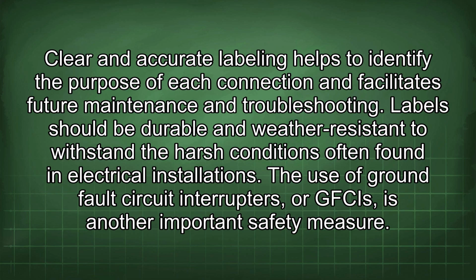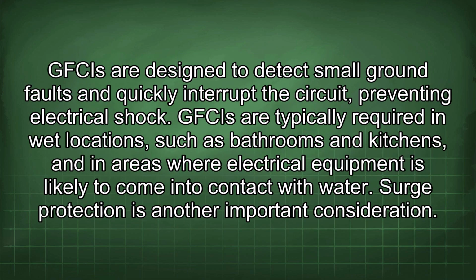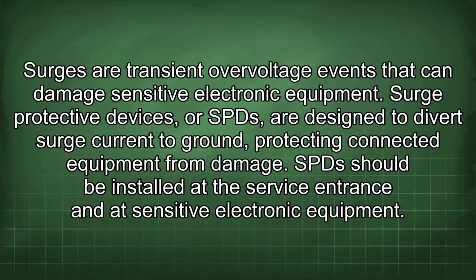The use of ground fault circuit interrupters, or GFCIs, is another important safety measure. GFCIs are designed to detect small ground faults and quickly interrupt the circuit, preventing electrical shock. GFCIs are typically required in wet locations, such as bathrooms and kitchens, and in areas where electrical equipment is likely to come into contact with water. Surge protection is another important consideration. Surges are transient overvoltage events that can damage sensitive electronic equipment. Surge-protective devices, or SPDs, are designed to divert surge current to ground, protecting connected equipment from damage. SPDs should be installed at the service entrance and at sensitive electronic equipment.